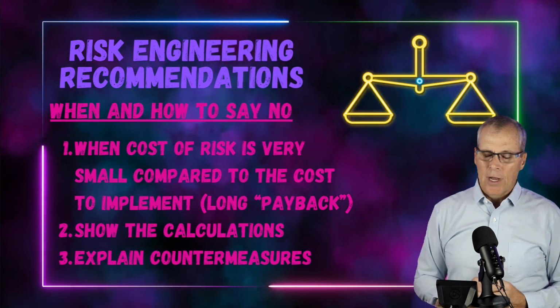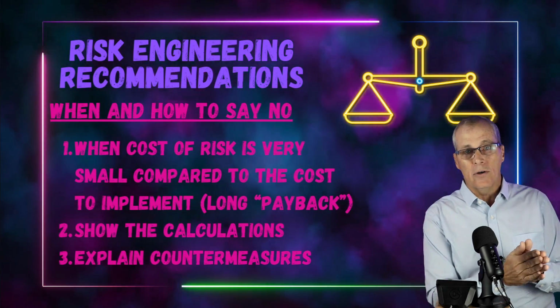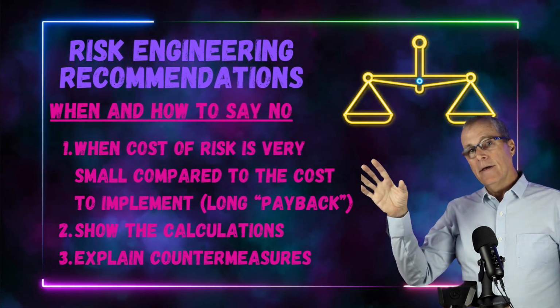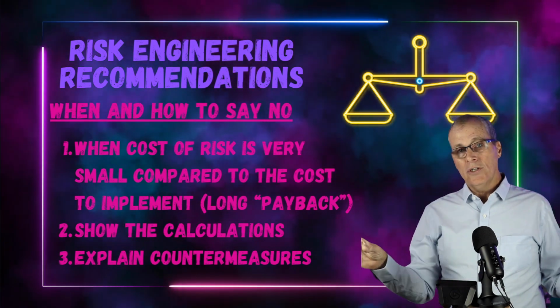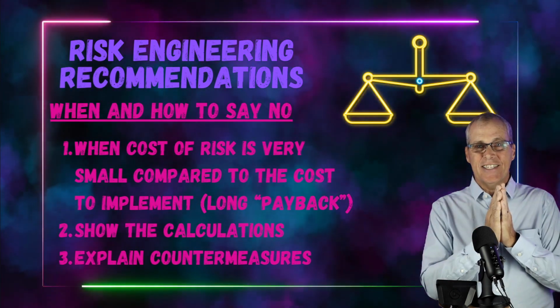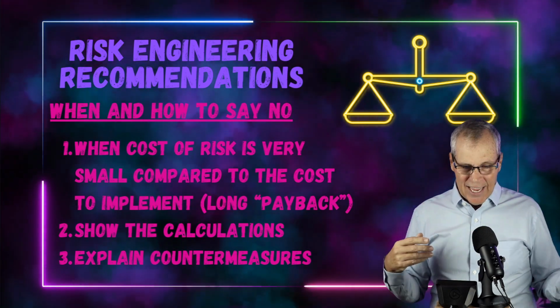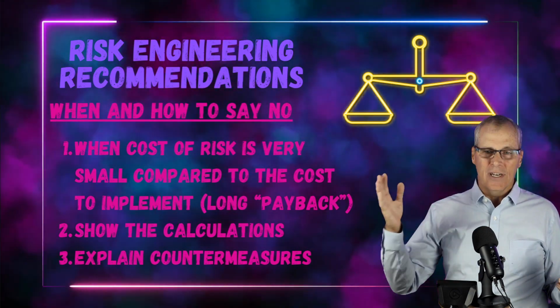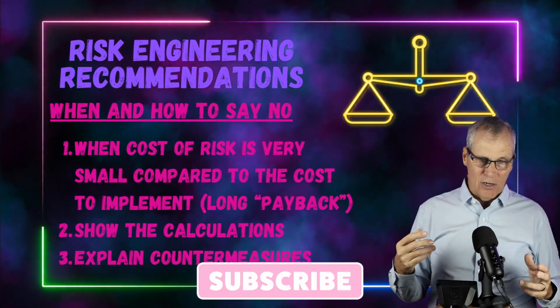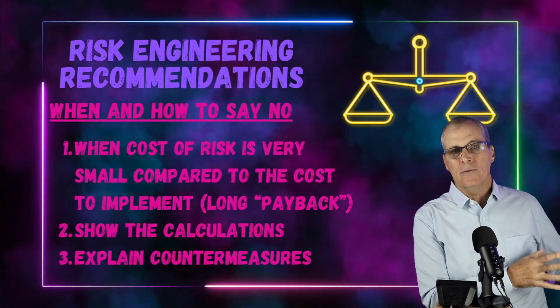An easy example, I use it all the time, is the $1 million firewall in between the $500,000 transformer and the $500,000 switchgear building. So if you have a $1 million firewall trying to stop from having a $1 million loss, then you really wasted your money. And you can talk about business interruption, and if you stop the fire from going to the switchgear building, that it's going to be a shorter turnaround. No, the outage duration is going to be based on that transformer.